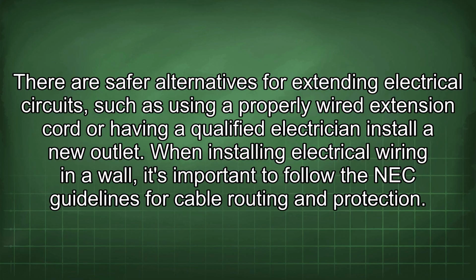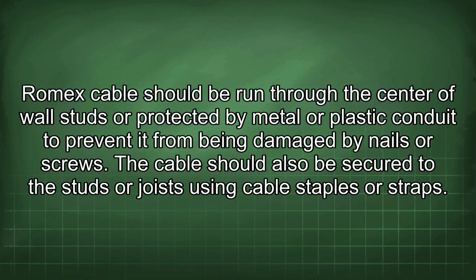When installing electrical wiring in a wall, it's important to follow the NEC guidelines for cable routing and protection. Romex cable should be run through the center of wall studs or protected by metal or plastic conduit to prevent it from being damaged by nails or screws.